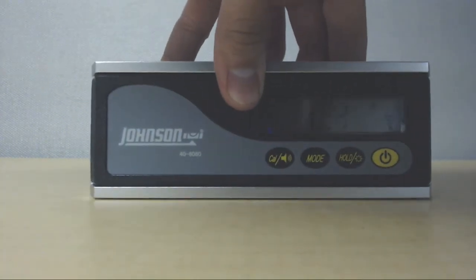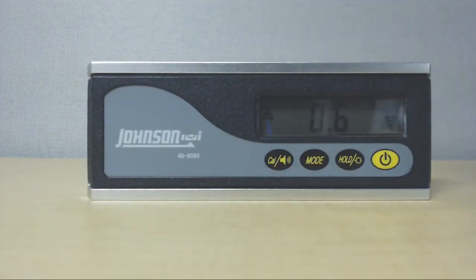Flip the device around. The measurement is 6/10 of a degree, which indicates that the device has been properly calibrated. Any measurement discrepancy greater than 2/10 of a degree between the front and back measurement indicates that the device has not been properly calibrated. In this case, the procedure needs to be repeated.